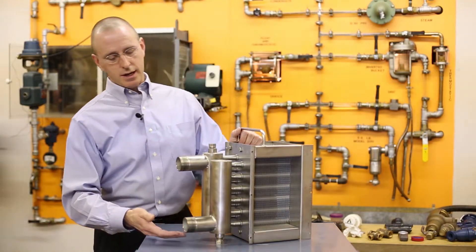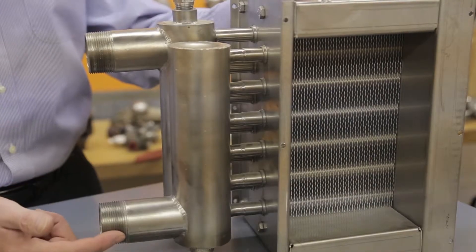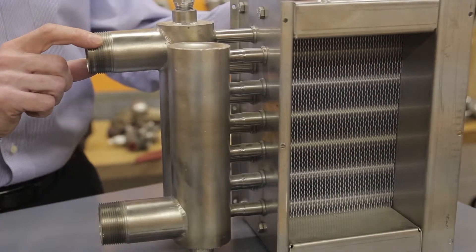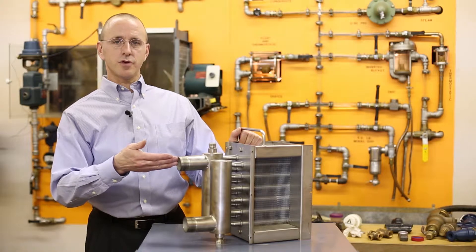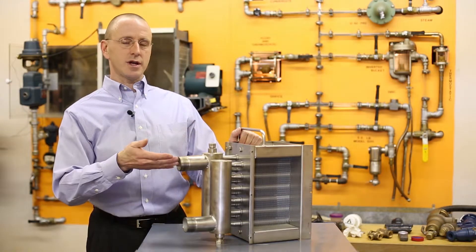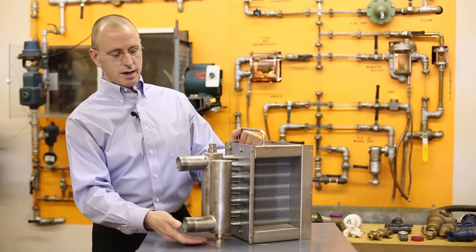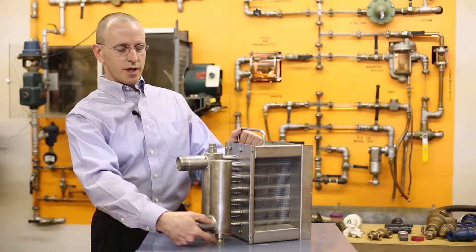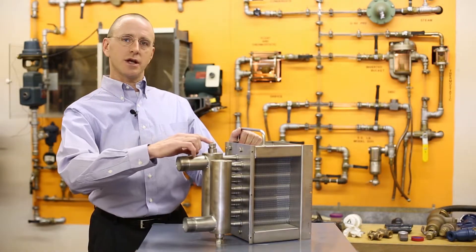The coils are circuited. The connections are located so that we've got an entering connection here and a leaving fluid connection here where we can provide full drainability and full ventability. We've also got alternate connections for a drain connection down here and a vent connection up here.